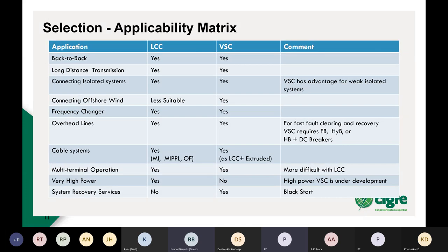So looking then, trying to summarize all of that and looking at an applicability matrix for LCC and VSC, we look at first, what are the kinds of applications you can use a DC in. For instance, in a back-to-back scenario, where you're connecting two systems, either of different frequencies or where you don't need to provide a DC line because the AC bus is already strong enough and can carry the power, then LCC and VSC are both applicable. There may be some advantage on VSC because they have integral reactive power control, whereas with LCC, you've still got to provide AC filters and switch shunt capacitors for reactive power control.